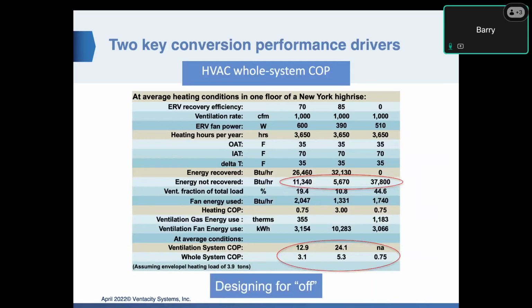A similar look at that, we looked at a 50-story office building in New York City. So this is right in NYSERDA's wheelhouse here for a project. This is a Local Law 97 approach that we were looking at for a 50-story office building, that are looking at a very large fine if they don't reduce their energy and carbon footprint. And so we analyzed what they have now, which is a COP of 0.75 for the whole system. They basically have boilers, cooling towers, and just raw air being brought into a space where there's an air handler that then heats and cools that air and distributes it per floor on that building.